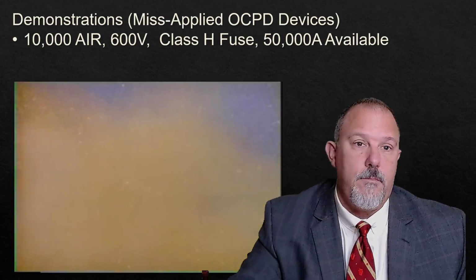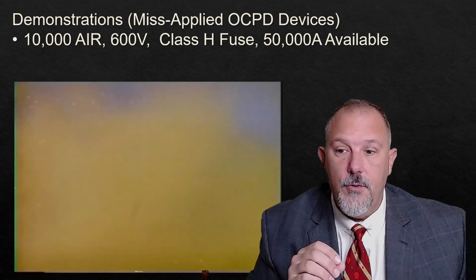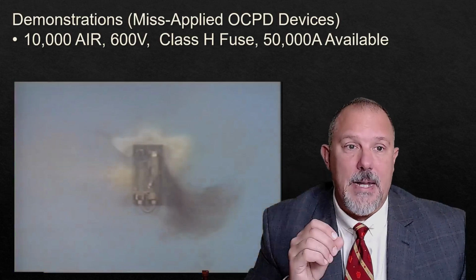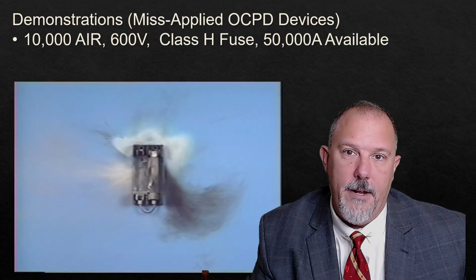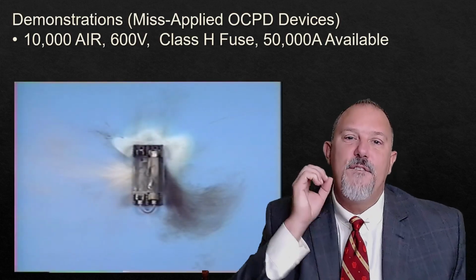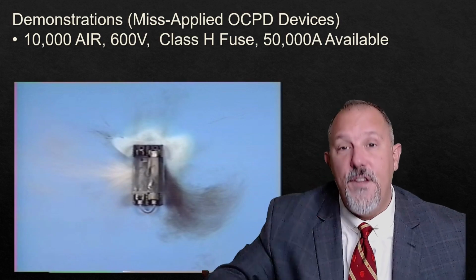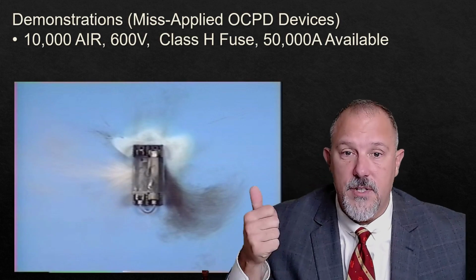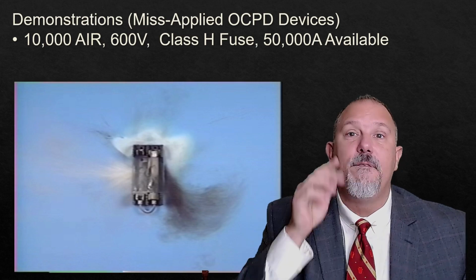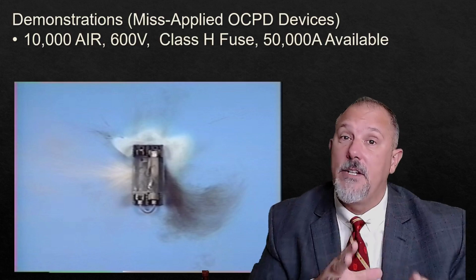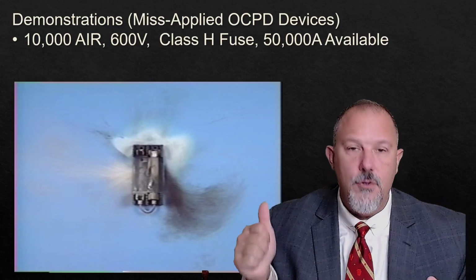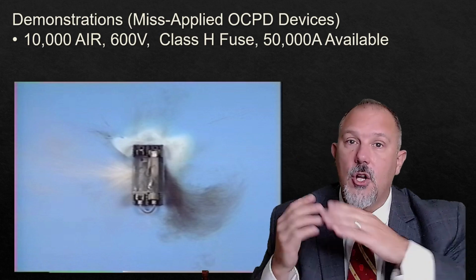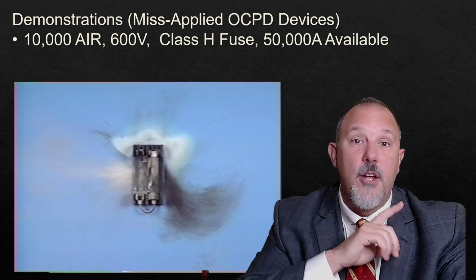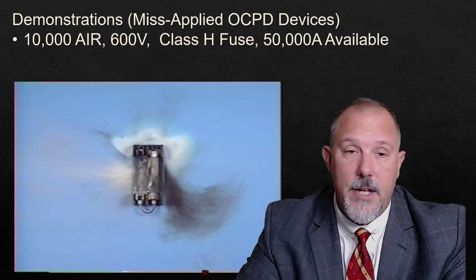Now this is a fuse. This is a fuse that was severely misapplied. It's only a 10,000 amp interrupting rating. This is a serious misapplication. I tried to stop the flow of 50,000 amps with a device that's only rated to stop the flow of 10,000 amps. This is an interrupting rating, not a short circuit current rating. That fuse was supposed to stop the flow of current, but it's only rated to stop 10,000 amps, not 50,000. Now let's take a look at a misapplied circuit breaker.